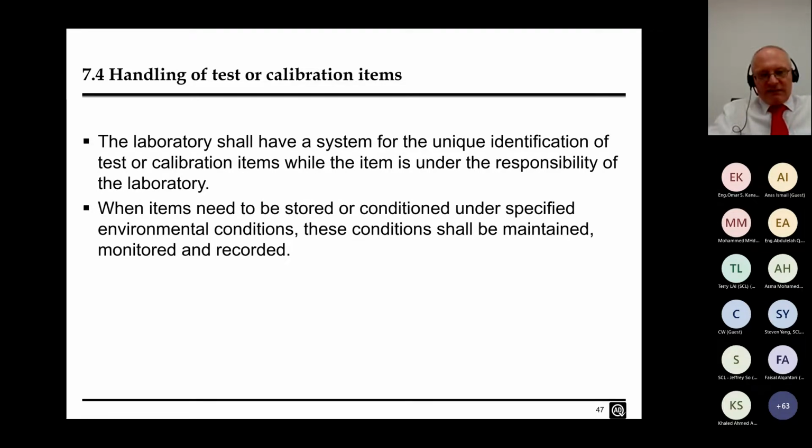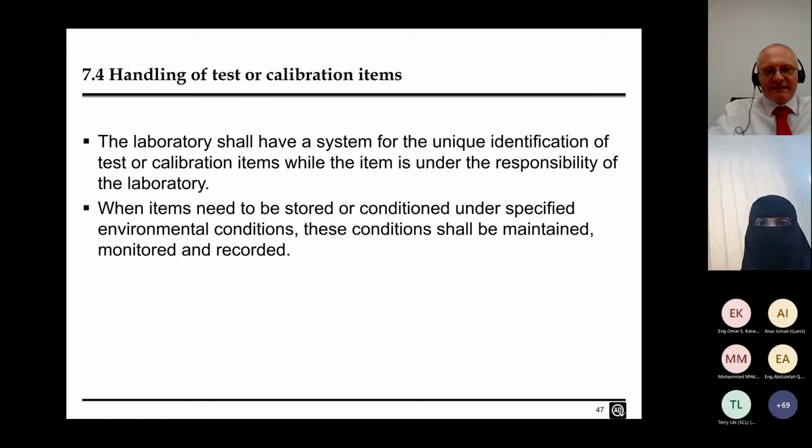Generally, in the sort of calibration of instruments that I've been involved with, each item has a unique identification. It has a serial number, it has a model number, so that we can track that item through the serial number. But for instance, in testing in pharmaceuticals, you may be given a sample of medicine, of tablets or capsules that have to be identified and managed.